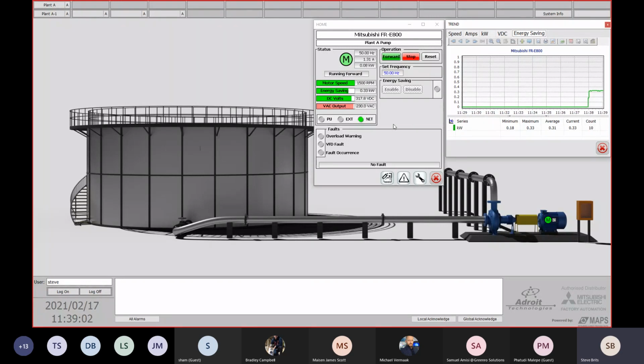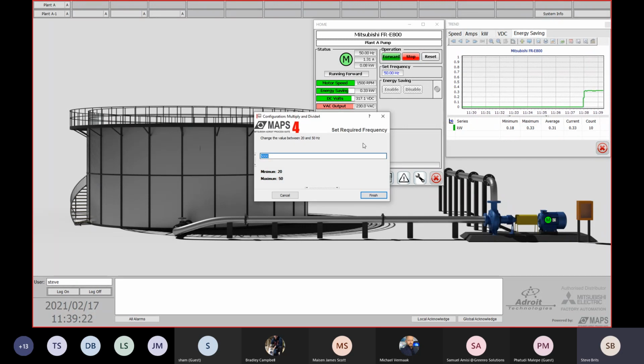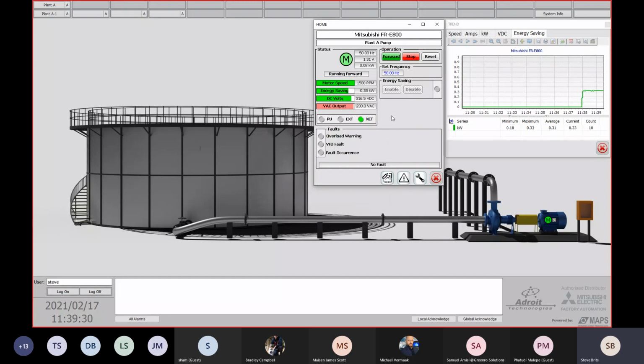Now, at the moment, I'm running the standard operation. No special parameters have been changed. So I'm getting a 230 volt output to the motor. If we reduce our frequency to the motor, it's going to start to slow down. I'm starting to draw less current. So that's where reducing it by 5 Hertz starts taking effect. But it's not a significant amount. Over time, it becomes quite a big amount, but over a short period, we're not really going to see a big difference.